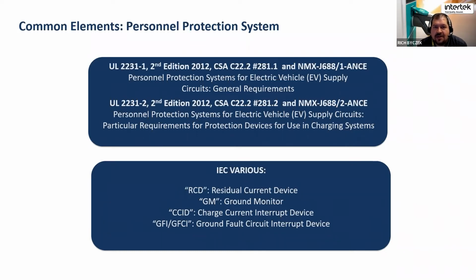So often the ground fault interrupt monitoring methods are not necessarily compatible, because you're dealing with one system using, call it a hot and a ground, and another system using two hots and no neutral pin and a ground. So there are some nuances there that make it difficult to have harmonized hardware without having multiple variations of how ground fault circuit interruption is monitored.